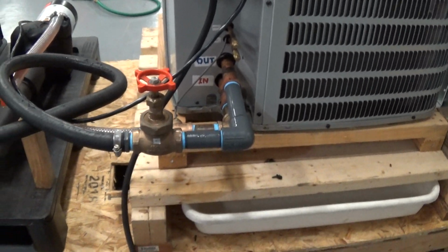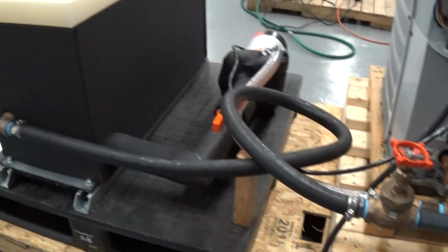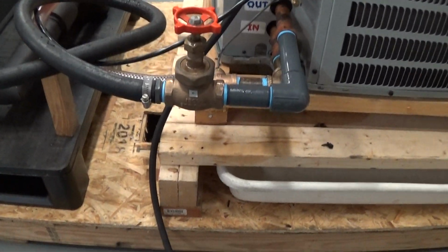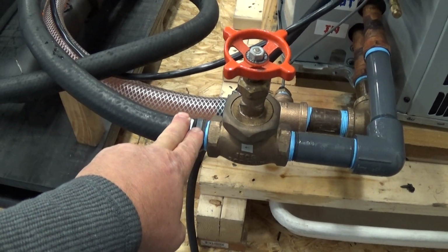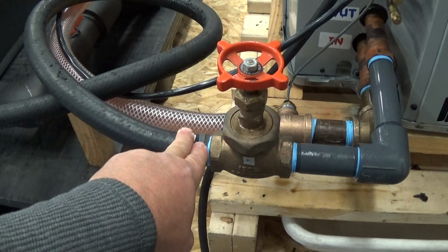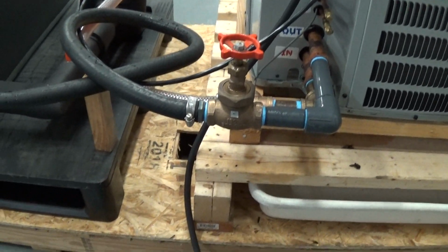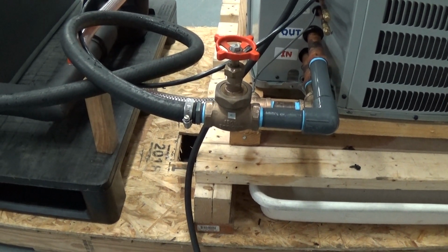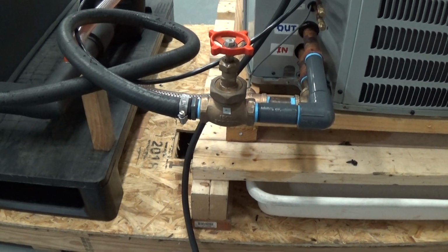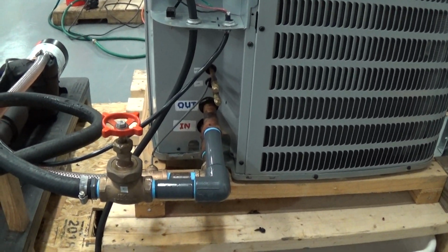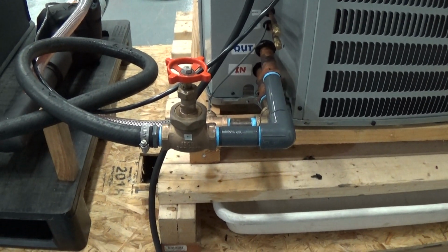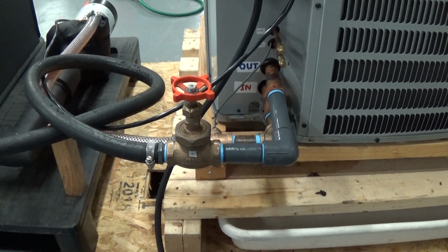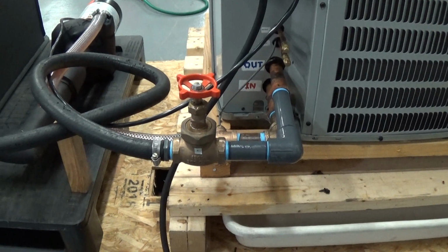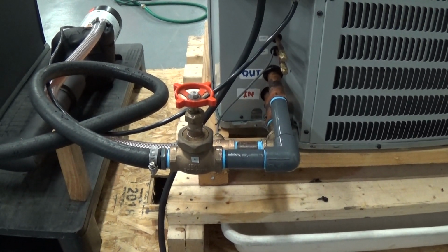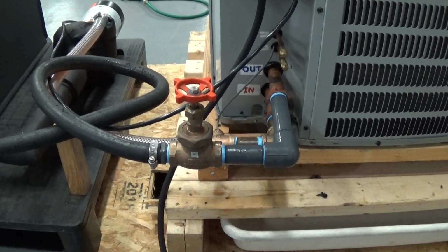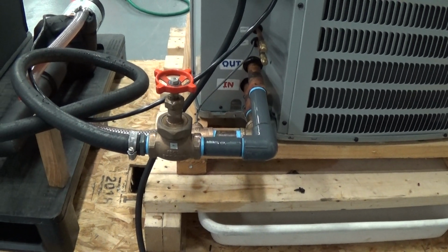So one of the most important things about this arrangement, unlike some other packaged chillers that we sell, is we need to talk about a bypass. So this is going to go out to your tank or tanks. Presumably all your jacketed tanks are going to have a controller and solenoid valve on them. When none of your tanks are calling for cooling, meaning all those solenoids are closed, we need some way in your piping to have some glycol come back to the chiller. In this case, because there's an internal flow switch, the best is to use a spring-loaded bypass valve, so that when all your solenoids are closed, the bypass valve opens and brings some glycol back to the chiller. But when you do have your tanks calling for cooling, we're using all the flow to go through the tanks, and that bypass valve will be closed. And just call us if you want us to explain that to you in more detail.